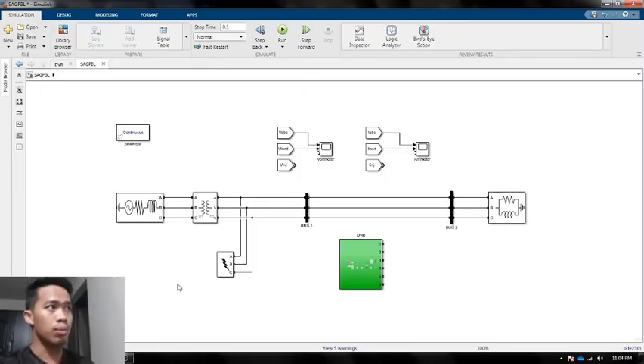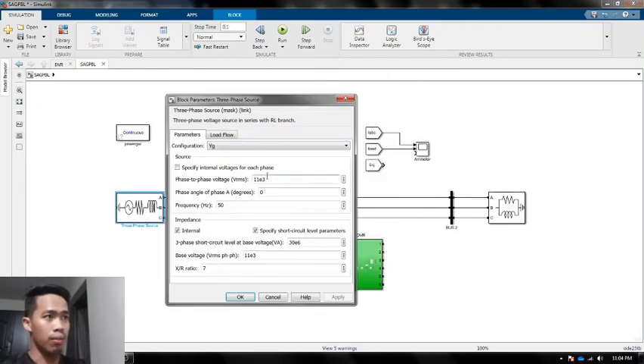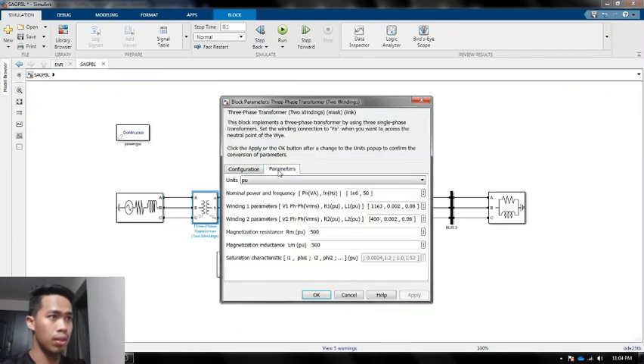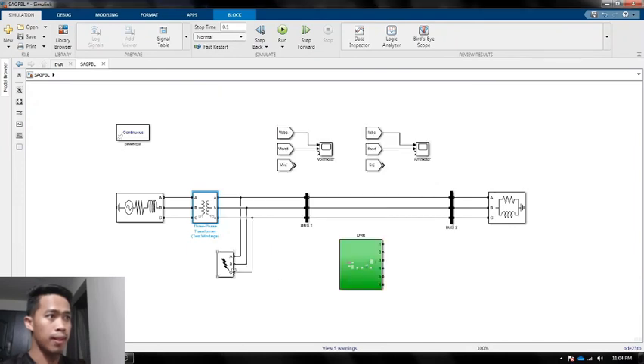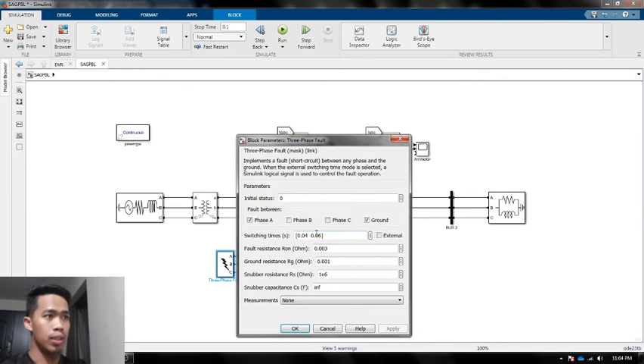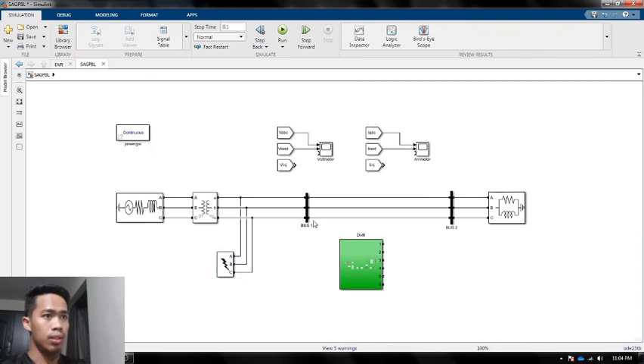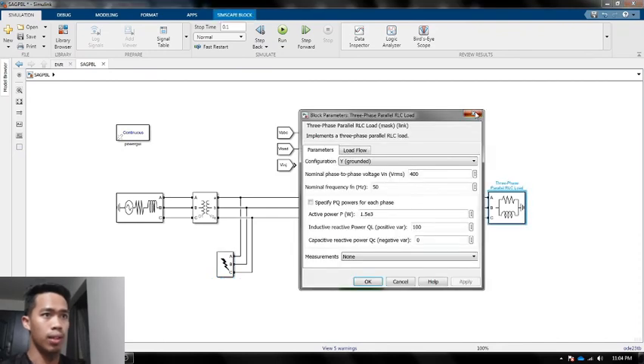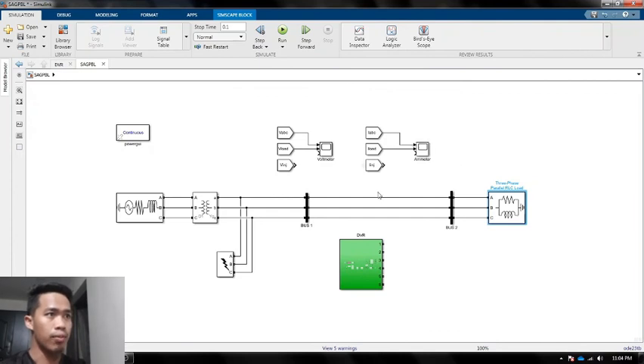So here is the simulation for our voltage sag. Here is the three-phase source which will generate 11 kV. The transformer will step down the voltage from 11 kV to 400 V. Then the third component is the three-phase fault, which is currently set from phase A to ground. The fault will occur from 0.04 to 0.06, and we have 2 buses here, and also the RL 3-phase load. We also have a voltmeter and ammeter here. The DVR will be explained by Ikmal after this. So let's run the circuit.